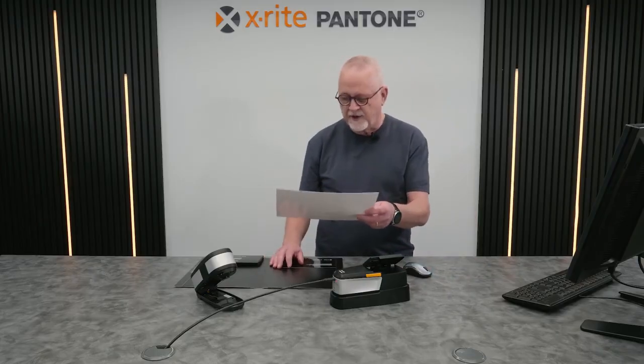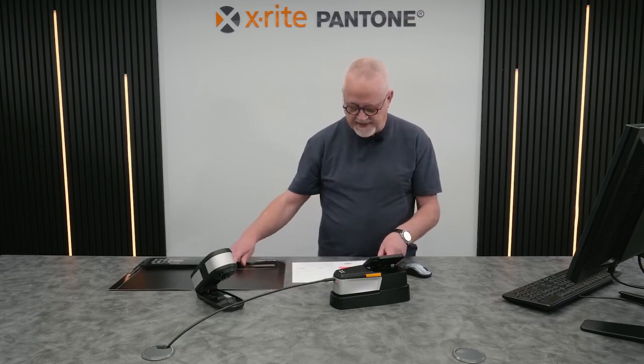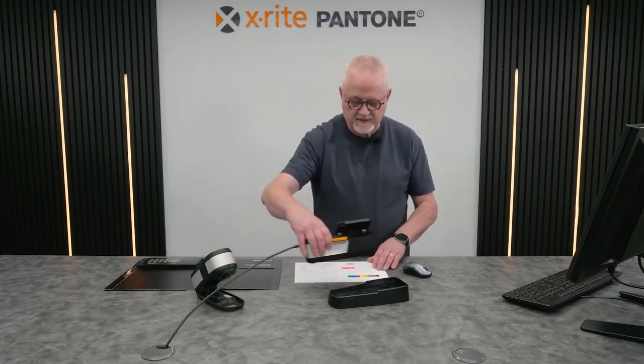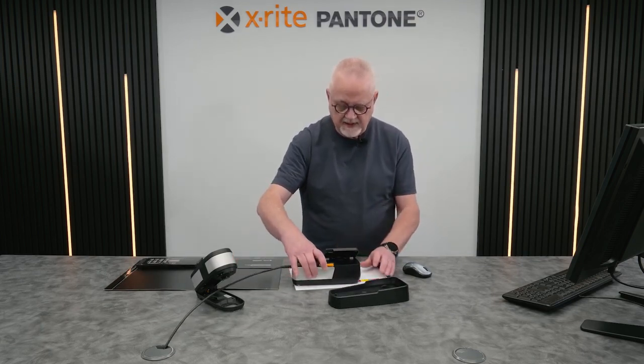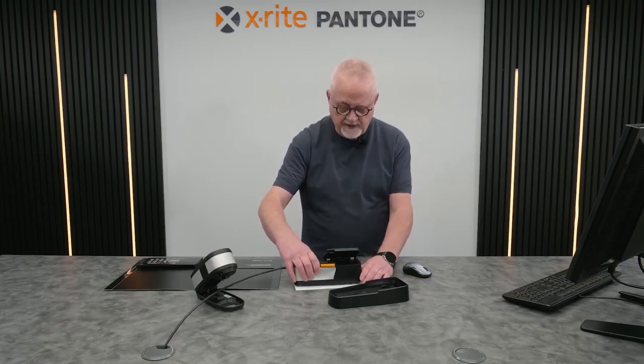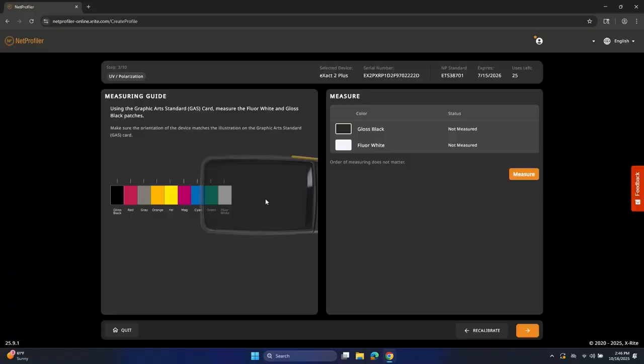So that's this card. Okay, I'm going to slide that out of the way a little bit so that I can take this down, and I can target it over the patch labeled fluor white. I'm going to take a measurement of that, press the measurement button, and you'll see I've got a green check mark and the word measured. Now I'm going to move it down and through the video targeting find the gloss black, measure that. It's a green check mark, and we have passed that part of the profile.